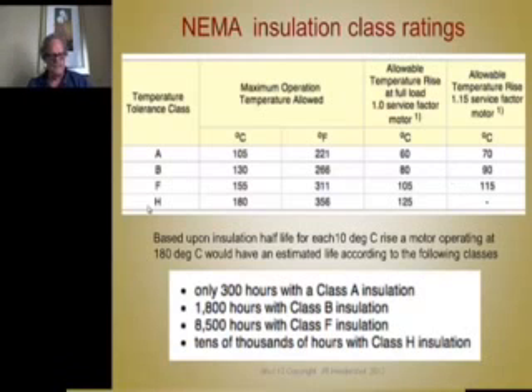The nameplate of every motor is going to have this rating, this temperature class on it, and these are peak temperatures in the winding. These are not surface temperatures of a motor, but the peak temperatures of the winding, so you have to use an insulation system, Class A, Class B, Class F, Class H, that's suitable for withstanding these continuous temperatures. I don't know if I have a slide here or not, but there's an old rule that for every 10 degrees in operating temperature of an electrical insulation material, you cut its life in half. That's the insulation half-life theory. So as long as these aren't exceeded, you'll get reasonable life out of the machine.